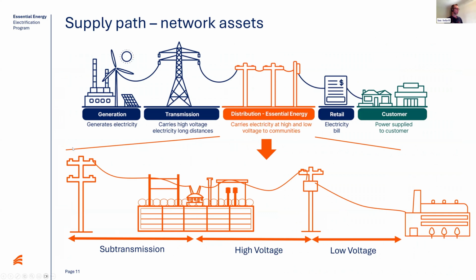We typically split into 3 components: sub-transmission, which is 33,000 up to 132,000 volts; the high voltage network, which is 33,000 down to about 11,000 volts; and the low voltage network, typically in the street, operating at 415 volts 3-phase. In terms of cost to serve, there are asset classes linked to these voltages, which then determine pricing.